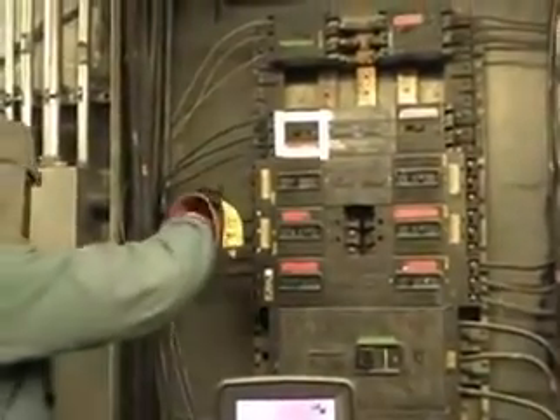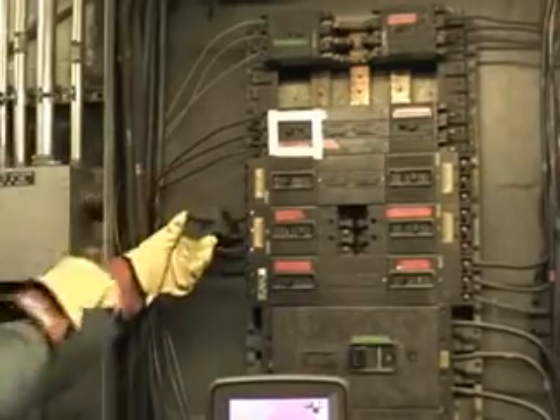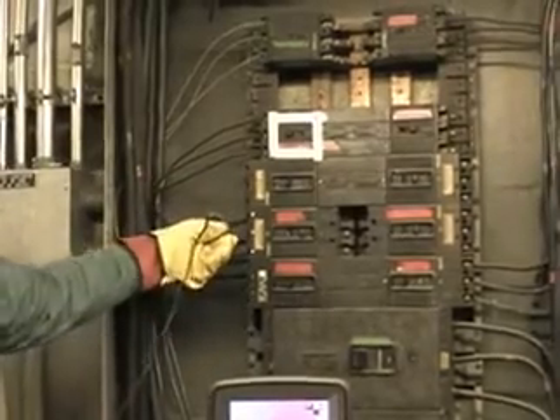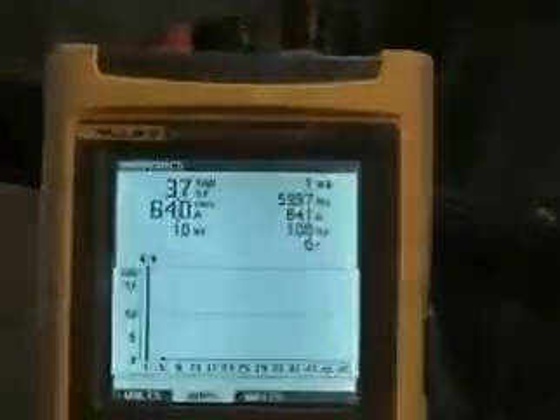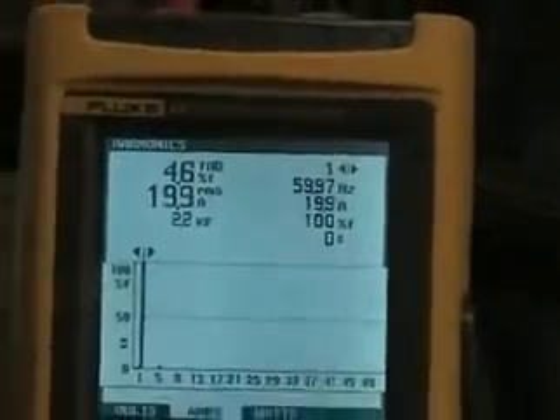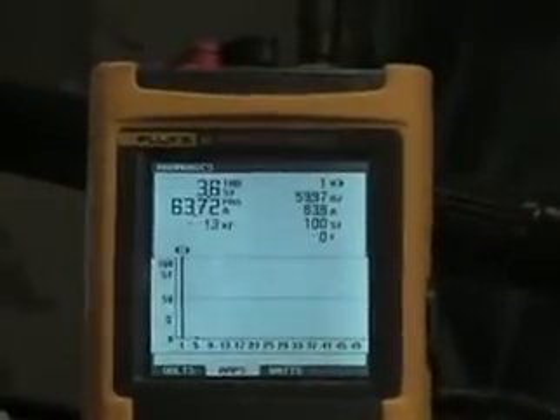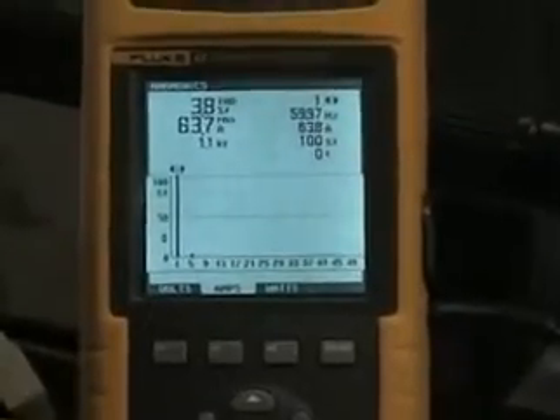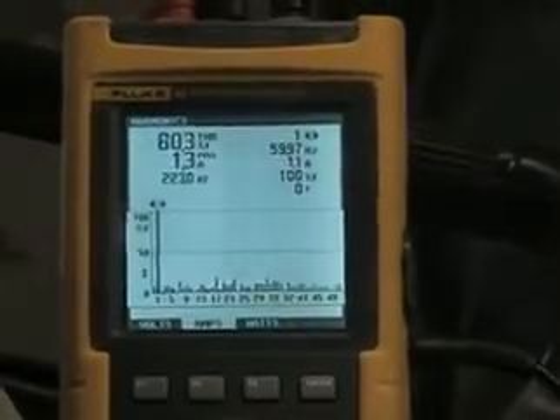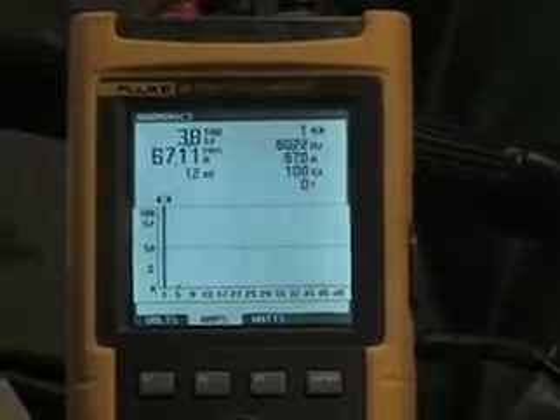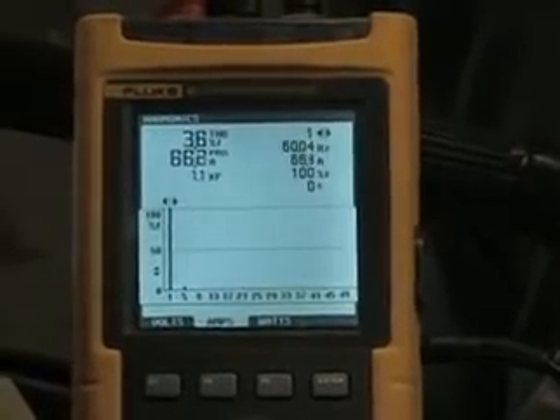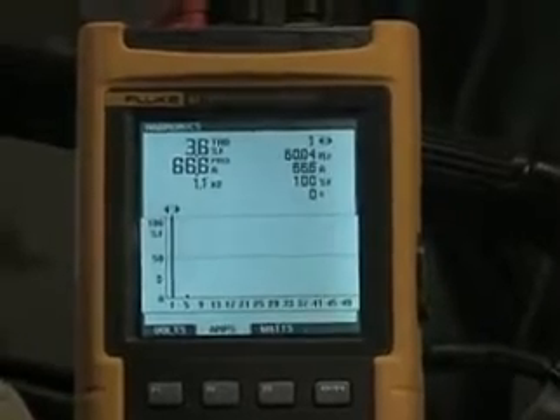We now will compare the actual load on this circuit breaker to its 90 amp rating. We will do this by utilizing a true RMS digital multimeter. We start with the A phase and see 64 amps with roughly 3.6% total harmonic distortion. Moving to the B phase, we again see 64 amps with roughly 3.8% total harmonic distortion. On the C phase, we see a slightly higher reading of 66 amp current draw and a relatively low harmonic distortion of 3.8%.